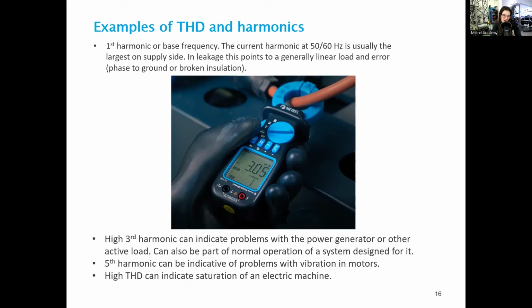High fifth harmonic, or unexpected fifth harmonic, can be indicative of problems with vibration in motors. So usually these are mechanical problems. Either the motor is not fitted well into its enclosure, or there are mechanical problems between the rotor and the stator. And this can show in the electrical system as high fifth harmonic.